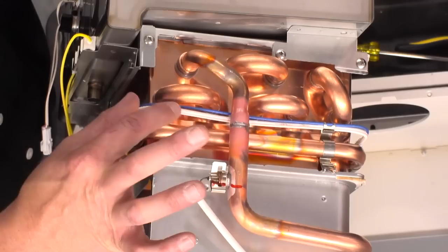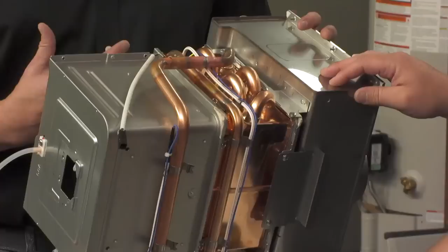All right, if you look at your heat exchanger, like Mike was saying, you've got this thermal fuse that wraps all the way around the unit. If this thermal fuse sees temperatures of over 430 degrees, it's going to open up. The only way you're really going to see that is if you have a breach in the heat exchanger, or you've got a hole, or flue gases are getting out. It may have a bad gasket, but it's probably going to be from a breach.